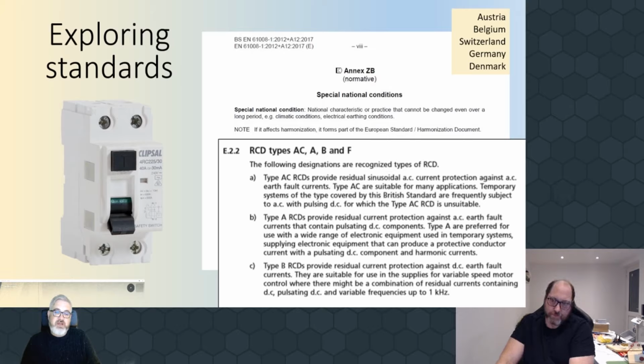So with all this digital technology and this DC threat, because I do see it as a threat, the inspection and testing criteria potentially may need a slight amount of tweaking, maybe for the inspector to look at the performance of the electrical installation during normal operation. So rather than doing a periodic at night or out of hours, there may be some inherent value in doing some inspection and testing or observation during the day.